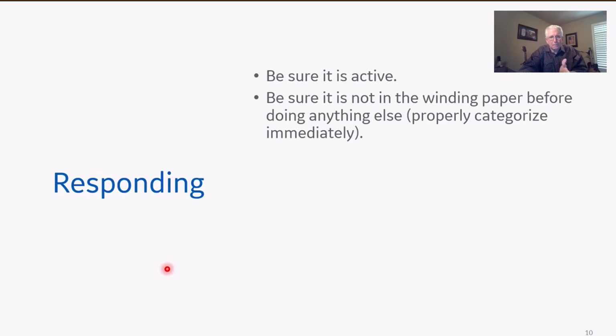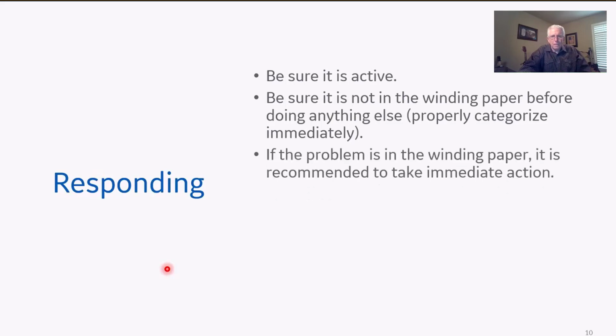So we're able to actually tell where this problem is - this is all about improving the odds. If the problem is in the winding paper, you'd want to take immediate action because that winding paper is kind of important. If you damage winding paper, that transformer is coming off the pad and getting replaced, and it gets expensive. If you catch it early enough, there are things you probably can do. By the way, I've seen several transformers where the paper was going bad, and only within the last month or so did any hot metal gas start to generate.